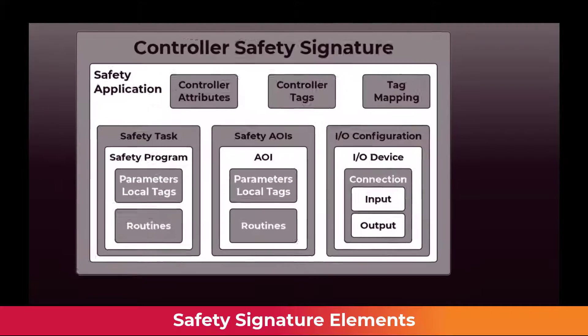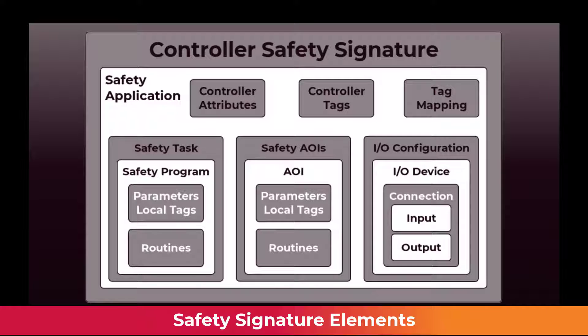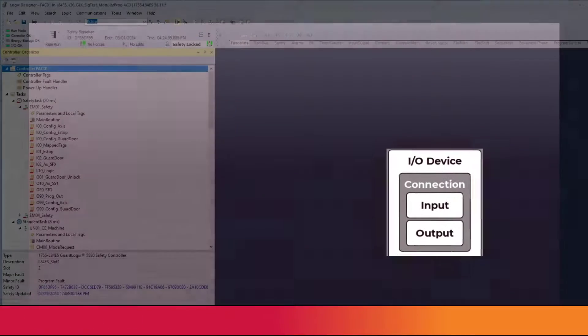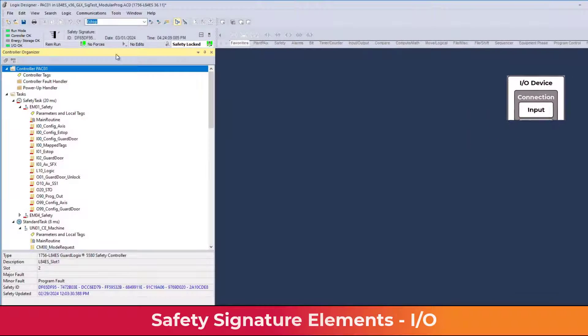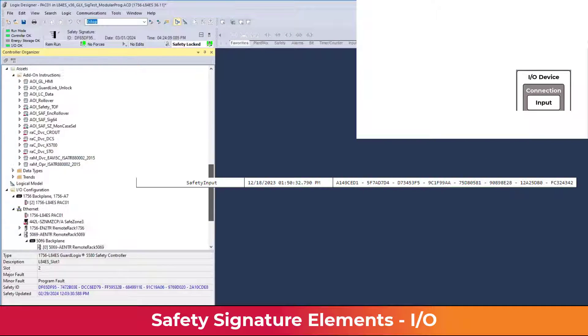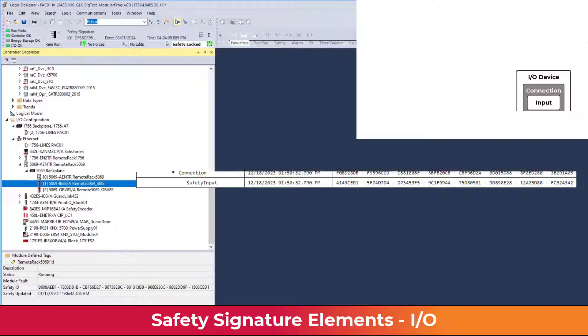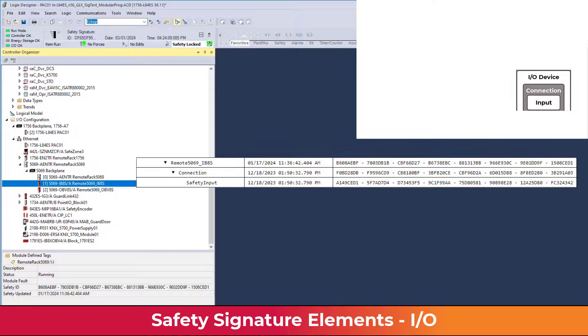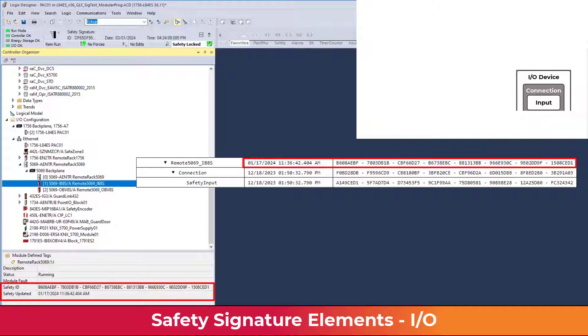To understand the different levels of the safety signature elements, let's start from the most basic level and build an entire controller safety signature. A safety input device has a safety input signature, a connection signature, and an overall device signature. These three signatures are present for each safety input device in the IO configuration.